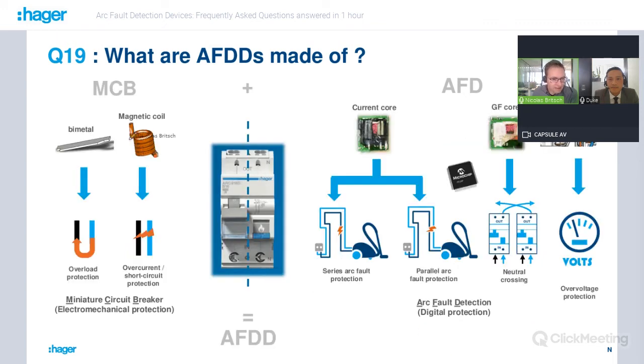On the left side, you have, of course, the MCB, so the bimetal first, which will bend itself to trip the product according to the temperature rise created by the current flow. And then you have the magnetic coil here, which will create a magnetic field to move the actuator that will trip the product in case of short circuit. And then you have the current core of the AFD part, which will measure the current with high precision. And this will allow the detection of both series arc fault protection and parallel arc fault protection.